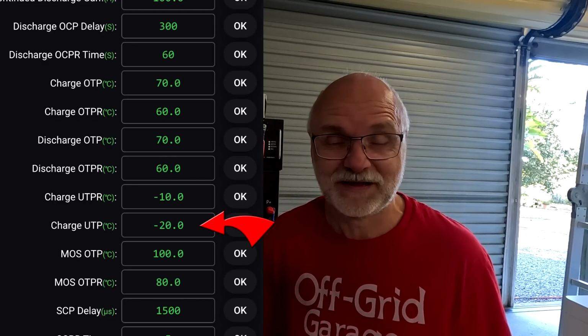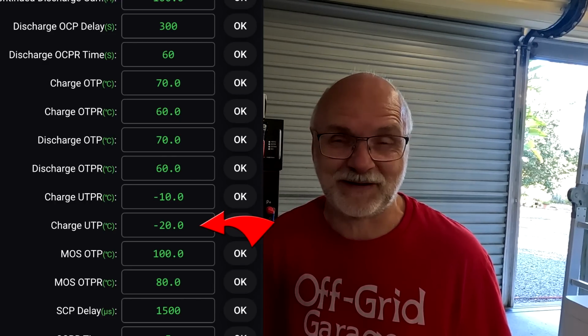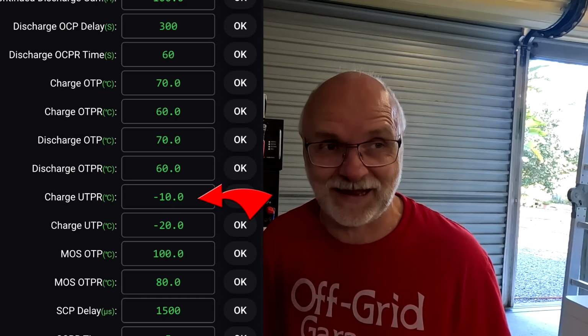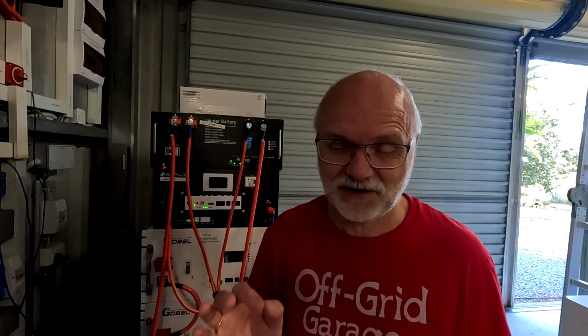Next, the default charge under-temperature protection. As per factory default, the under-temperature protection is still at -20 degrees Celsius, with recovery at -10 degrees Celsius. This is obviously insane if you're using lithium iron phosphate or any other lithium battery, since you cannot charge lithium under 0 degrees Celsius without damaging it. This has been requested for years and still hasn't been fixed, even though they promised to put it on the list for the next version. They could just set the under-temperature protection to 2 degrees Celsius and recovery to 7 degrees Celsius, and everything would be fine with a safe margin.